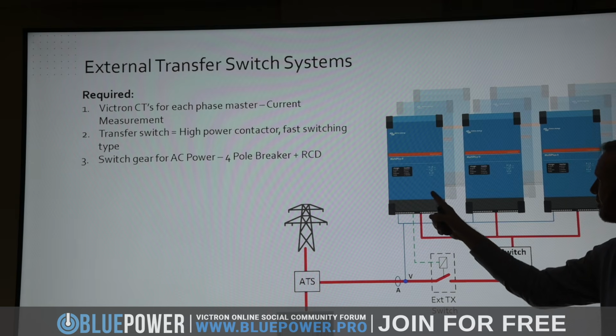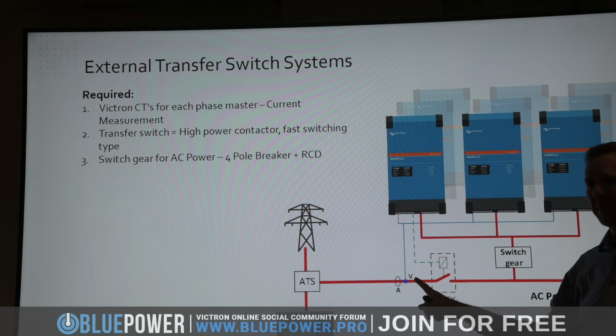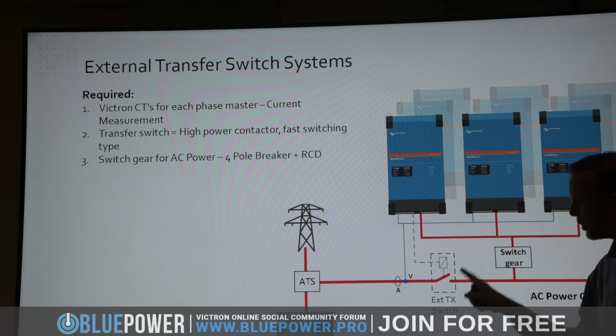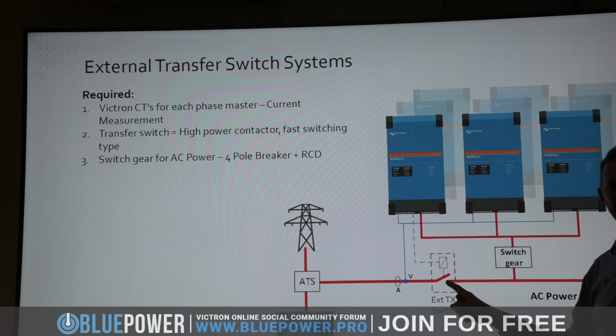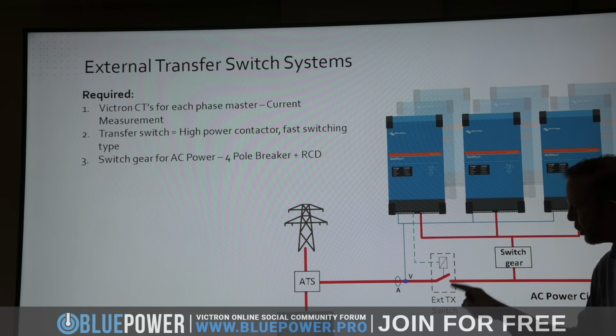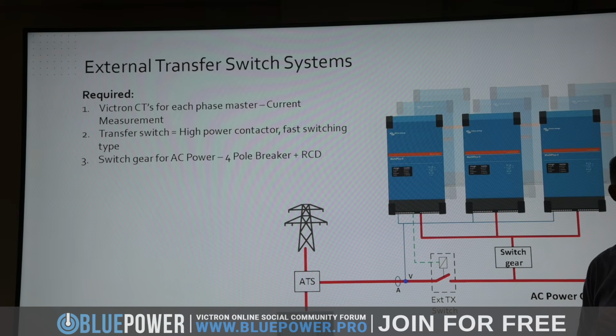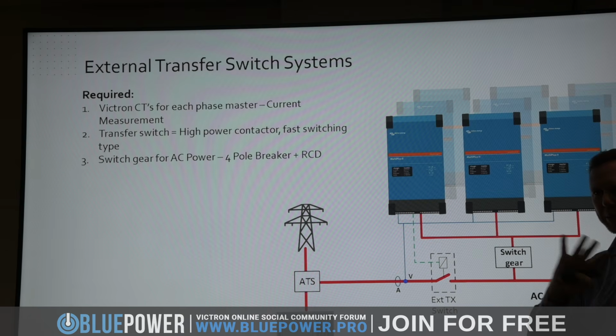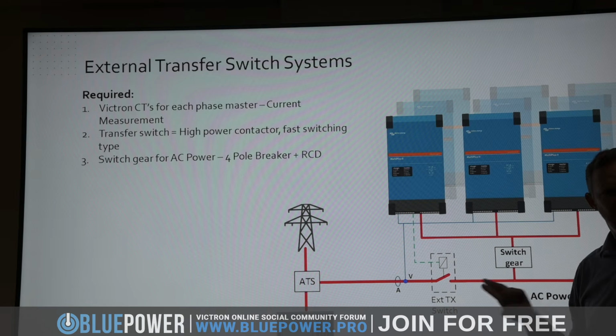What happens is the Multis sense the power here, then send a signal for this to close. If that takes longer than 80 milliseconds, they switch off, because that's too slow to connect and transfer power. So the quicker it can connect, 80 milliseconds is the absolute maximum - find something faster and it'll just work.